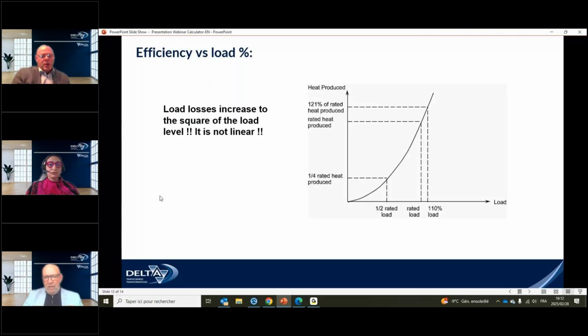Those losses are not linear, they're exponential. So the more you load, the more you have losses. At 50% load, you will generate 25% of your losses, because the load losses in the winding increase with the square of the load. So 0.5 times 0.5 equals 0.25 times your full load losses. So the more you load the transformer, the less efficient it is, and when you reach 75, 80, 85%, your losses really increase. So just looking at a drawing and an efficiency level will not provide you the consumption of energy of that transformer and what your cost of energy is.